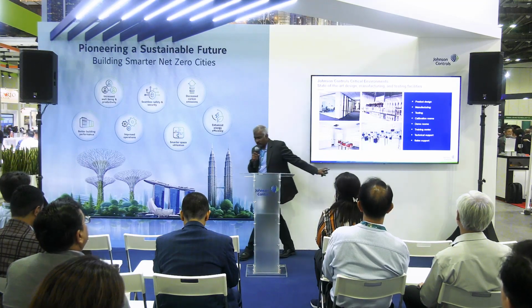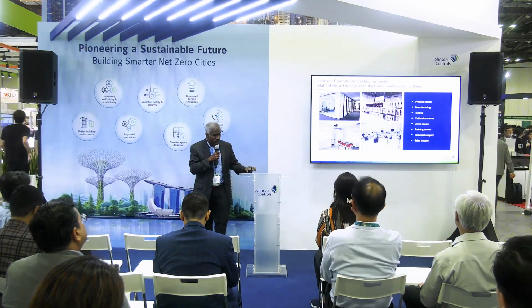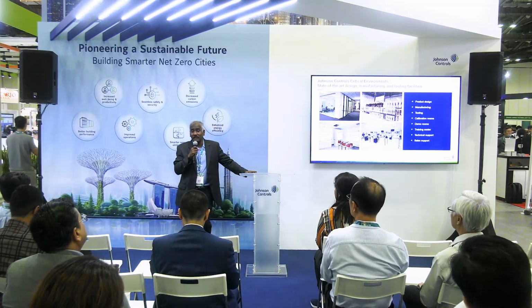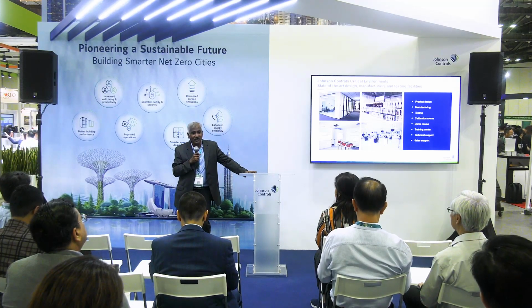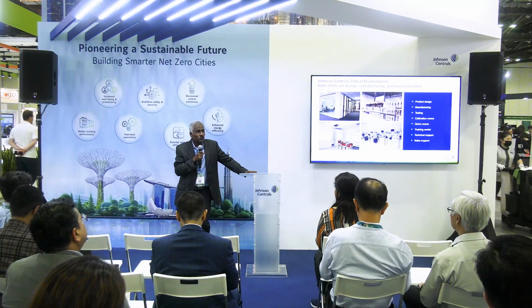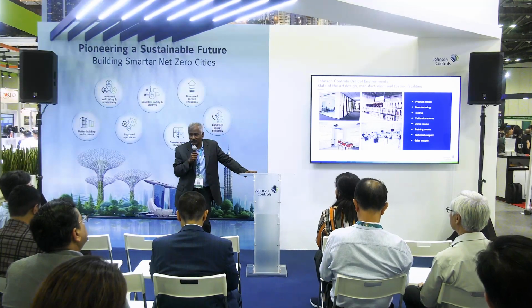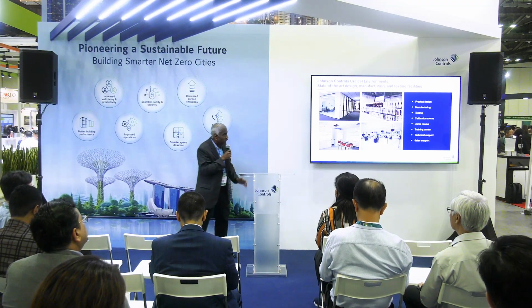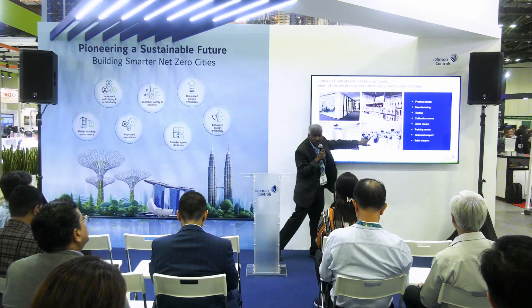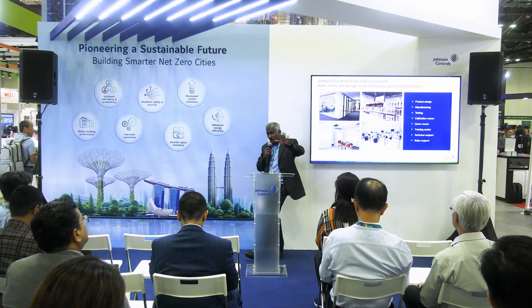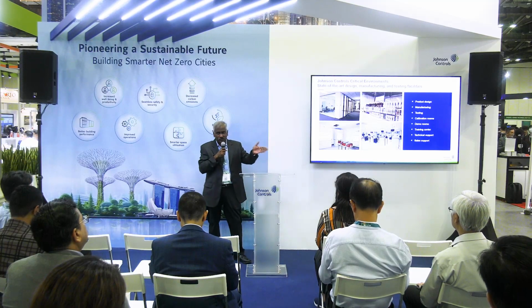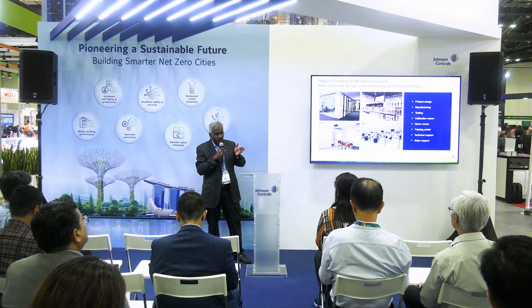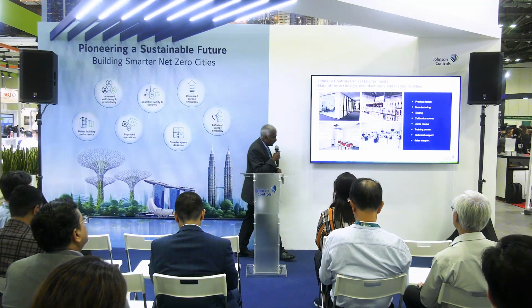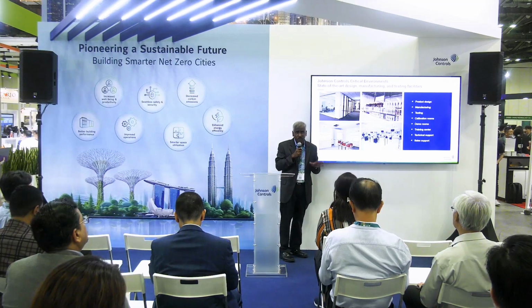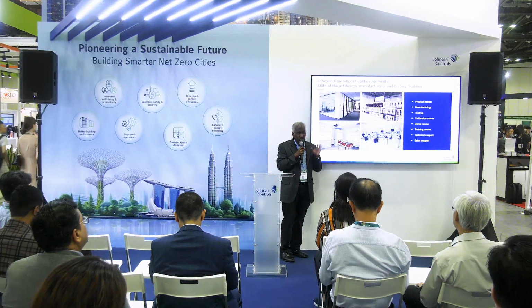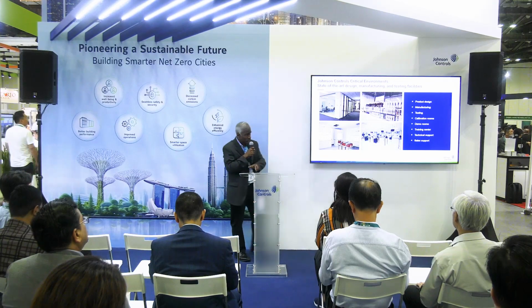One thing I didn't mention is that the Venturi valve does not have any sensors. You can ask how it maintains 200 or 300 or 400 CFM. It's mechanically calibrated at the factory, with something like 42 readings, each at 100, 200, 300, 400. Each one is calibrated, so it's mechanical. And there's a reason why. When you have VAV, there are a lot of challenges, which I'm going to talk about later.